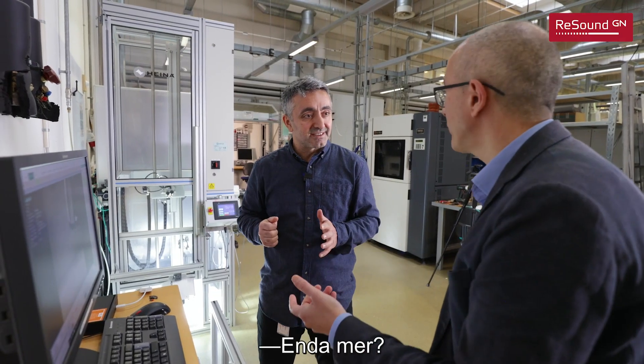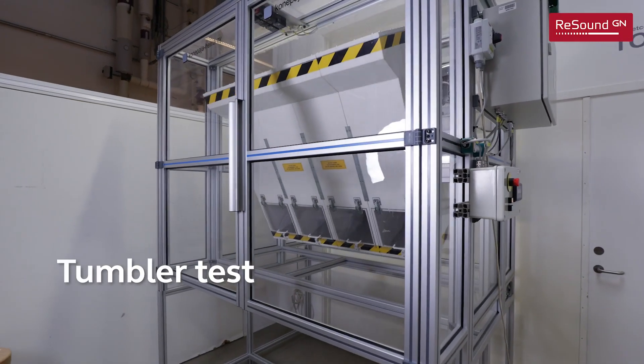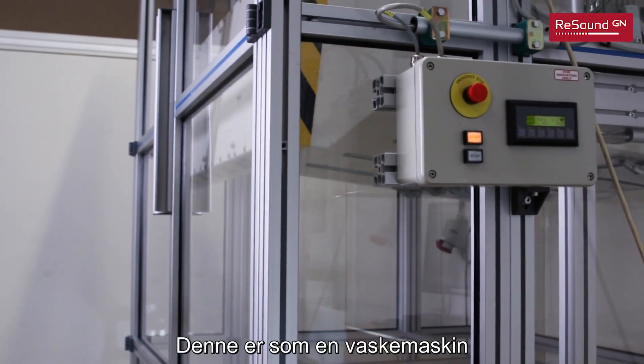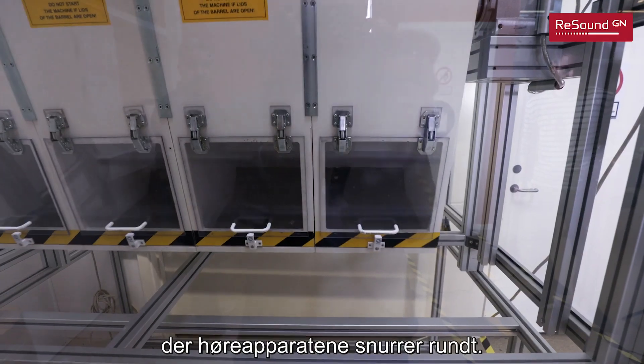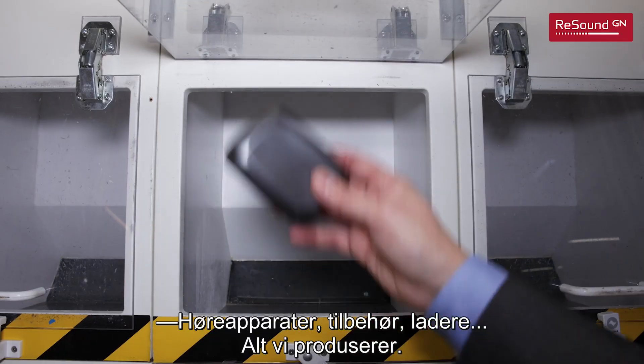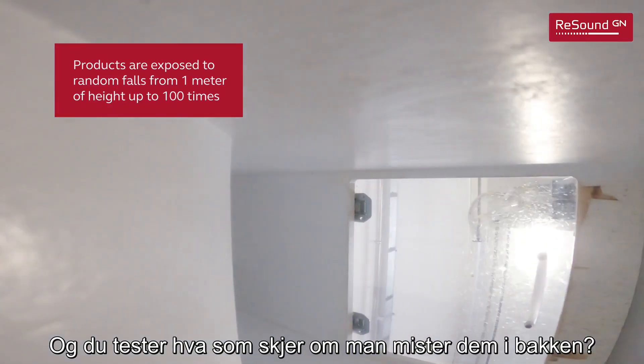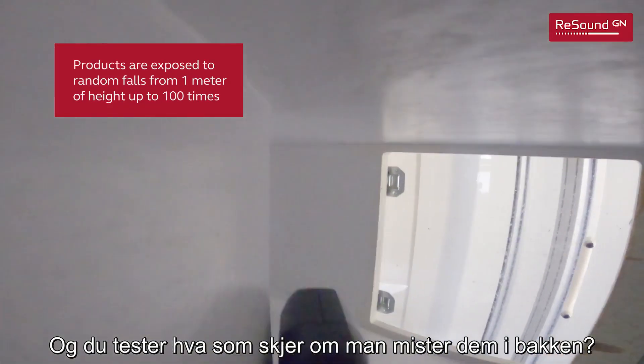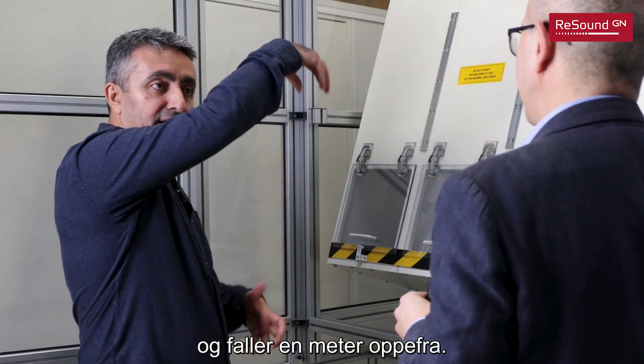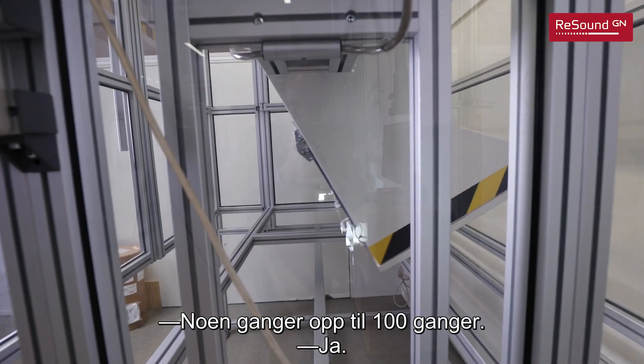So this is like a fancy washing machine where the hearing aids are spinning — hearing aids, accessories, chargers, everything we produce. Everything goes to the washing machine. And you are testing for random falls? Random falls — they are hitting each other, sidewalls, and falling from one meter high, sometimes up to 100 times.